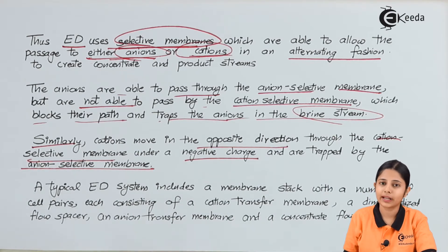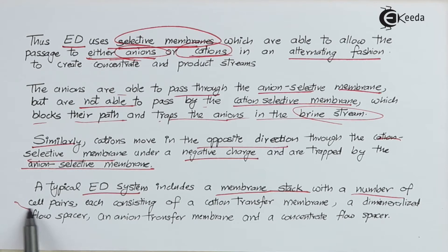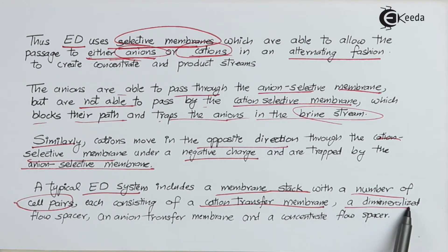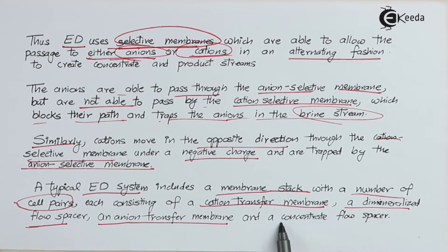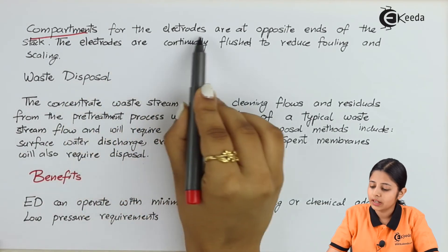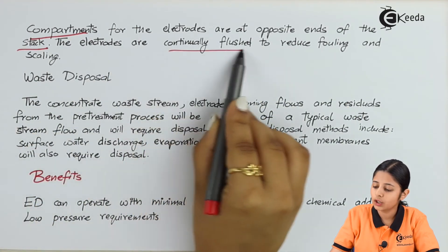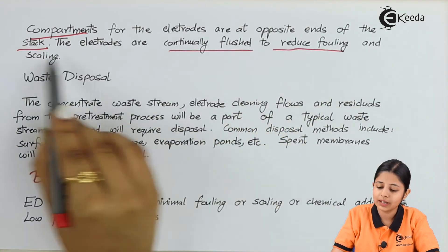A typical ED system includes a membrane stack with a number of cell pairs, each consisting of a cation transfer membrane and demineralized flow spacer, an anion transfer membrane and concentrated flow spacer. Compartments for the electrodes are at opposite ends of the stack. The electrodes are continually flushed to reduce fouling and scaling.